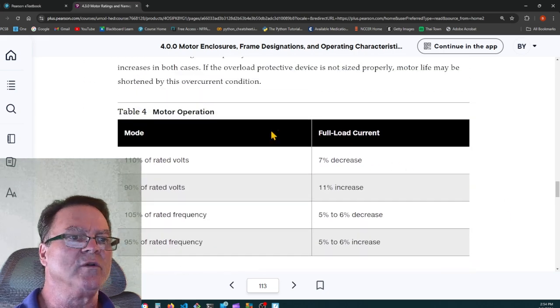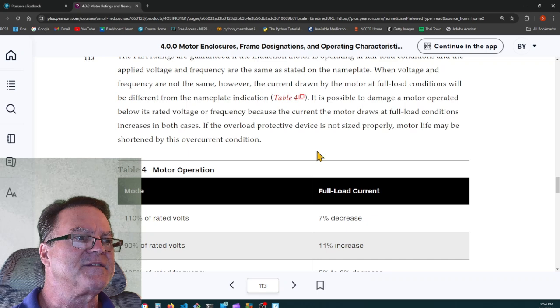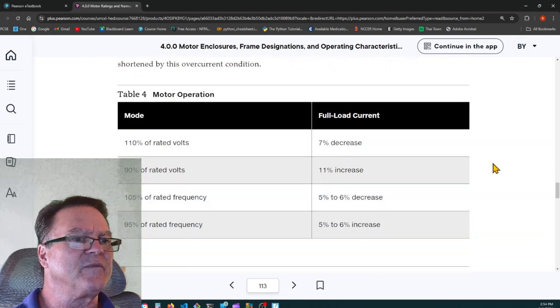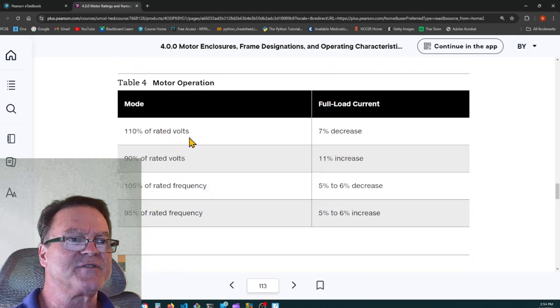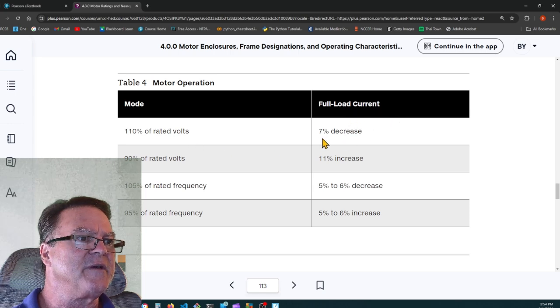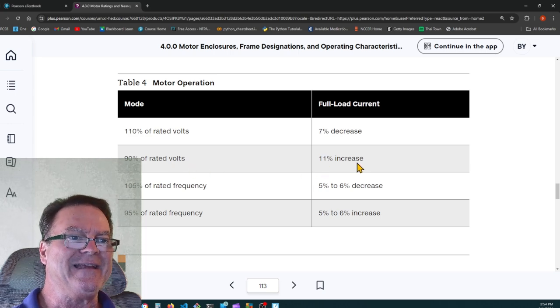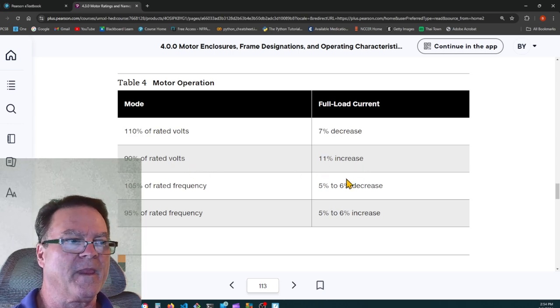So here's a code letter. It says service factor. Well, I'm not sure if they're talking about that. At 110% of rated voltage, there's going to be a 7% decrease in the full load current. At 90% of the rated voltage, there's an 11% increase in the current.